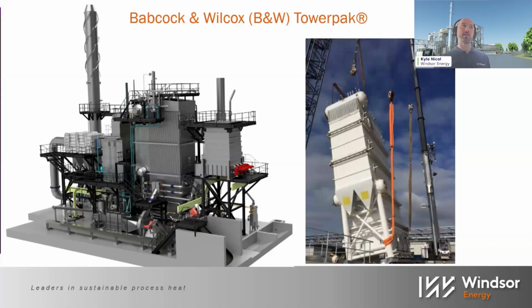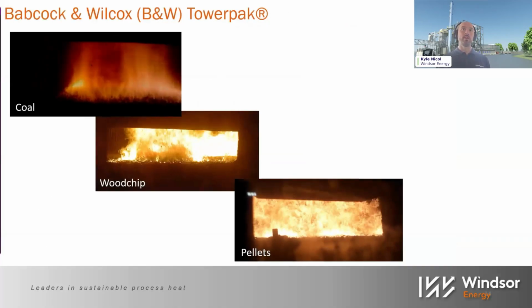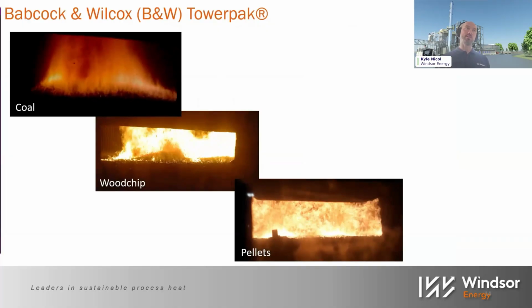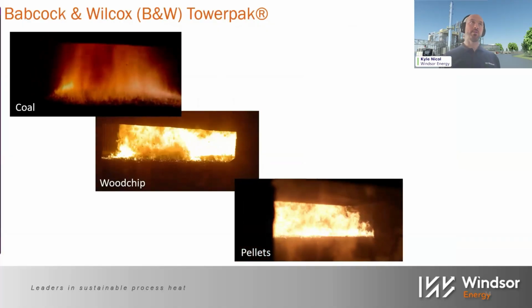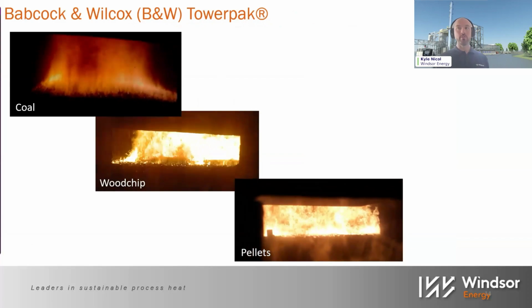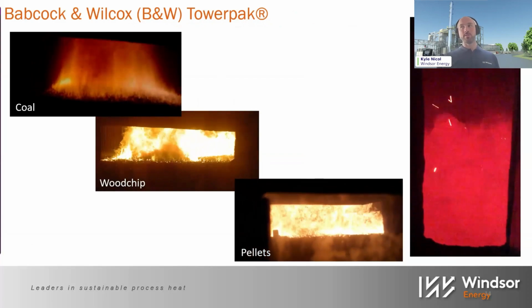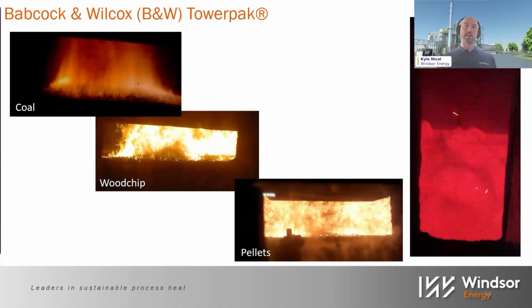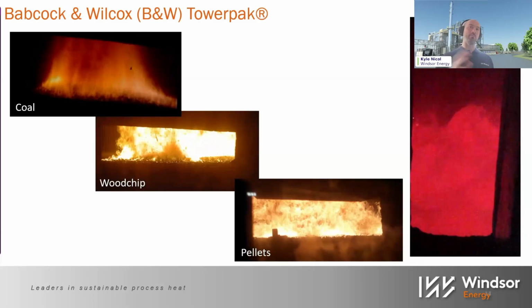And so Windsor designed and installed the Babcock and Wilcox Towerpak boiler, which is under license from B&W. They range from 10 to 50 megawatts. The Towerpak boiler has the ability to pair with different moving grate types, or even a bubbling fluidized bed, which is that image on the right there. The reason there are different grate types is to provide for different types of biomass. I won't go into details on which type favors which grates, but we can do that work.